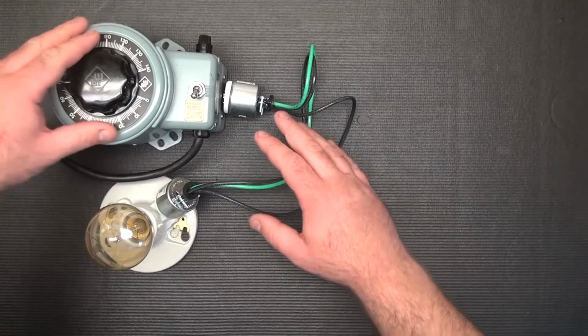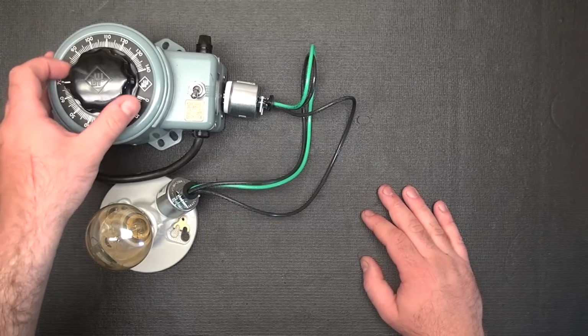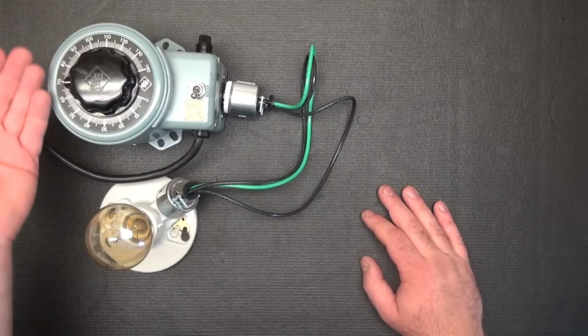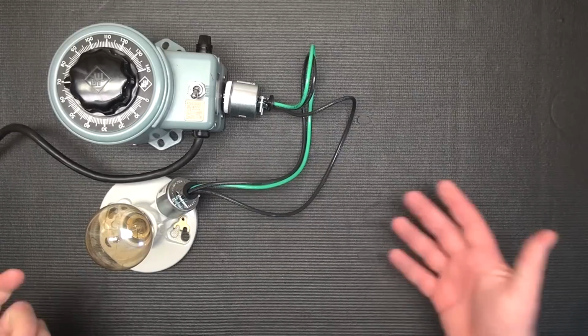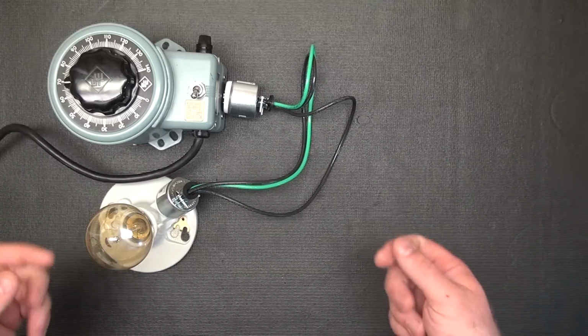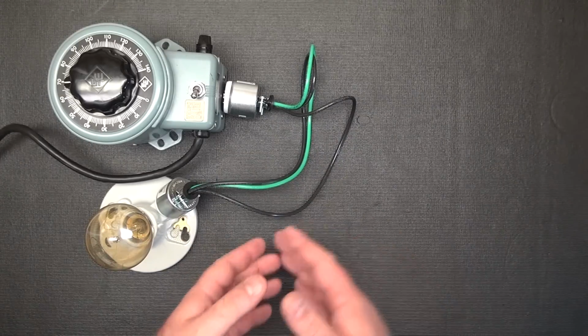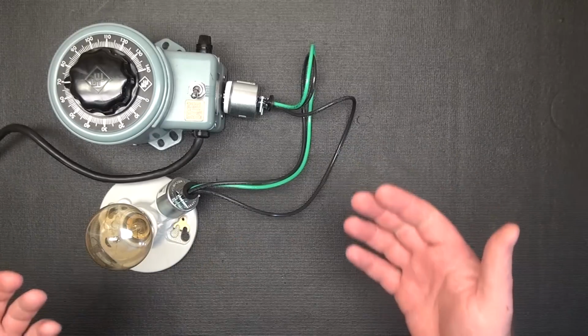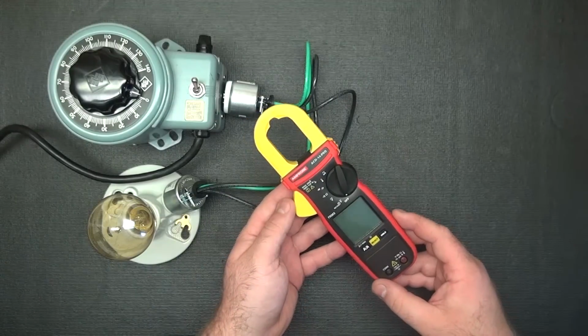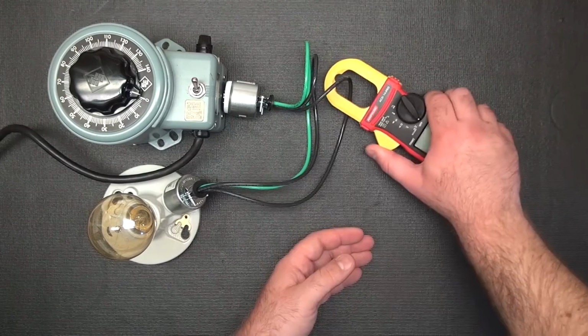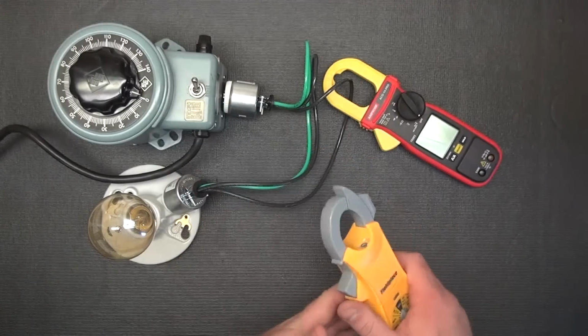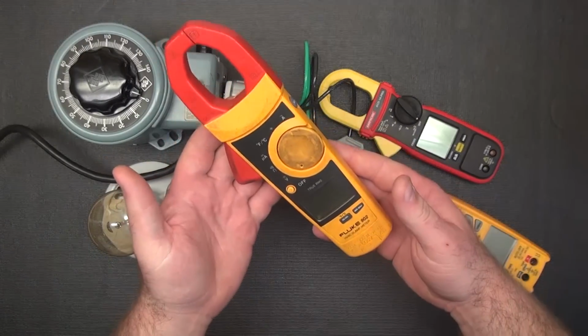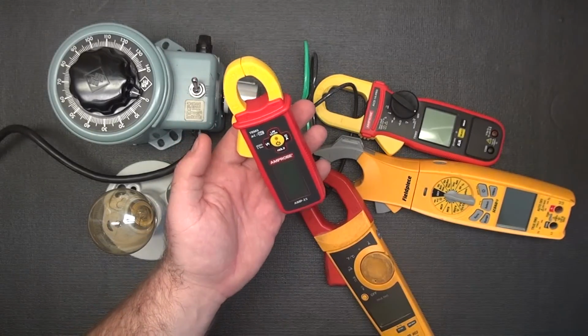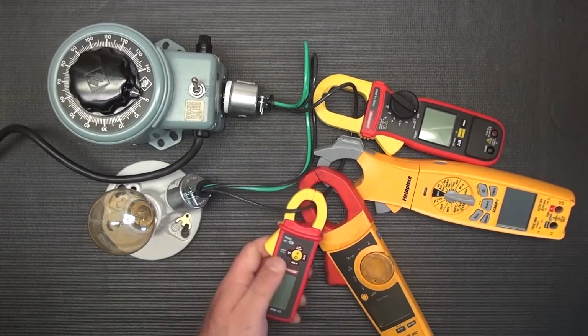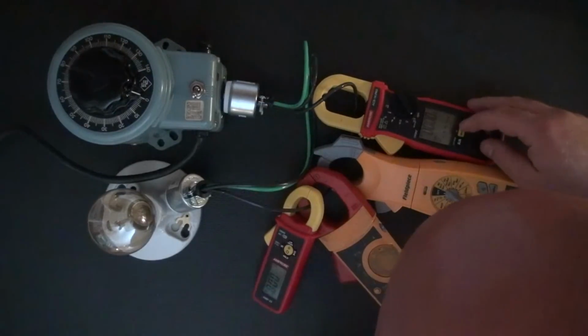We'll use my little Variac lamp here, which I can vary the voltage from 0 to 140, and we'll compare it to a couple other meters to see how it stacks up as far as calibration and response. Here we'll take the Amprobe ACD14 Pro, the Fieldpiece SC660, the Fluke 902, and the Amprobe AMP-25, and turn the backlights on all of them.